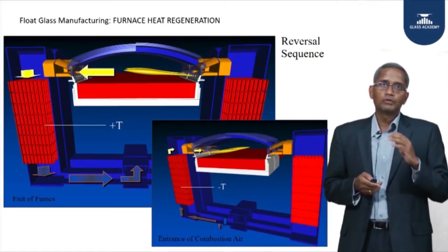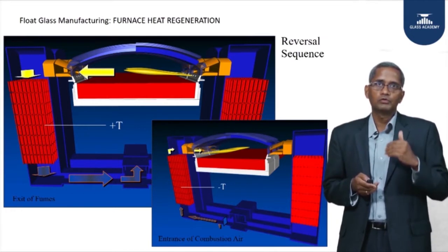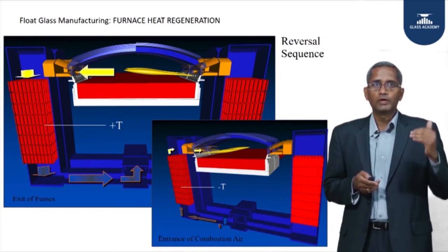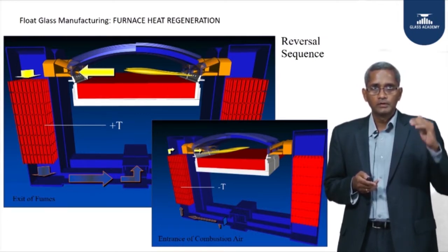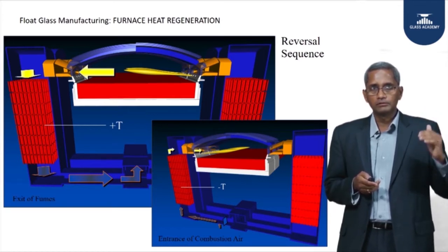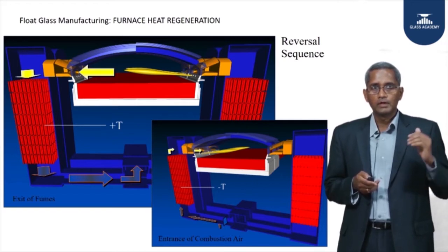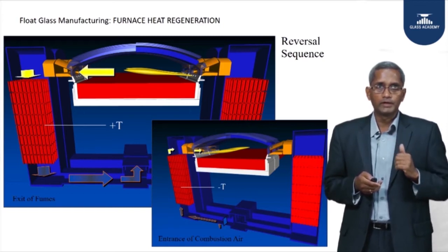In this process, for 20 minutes firing continues from the right hand side towards the left hand side, as seen in the background picture. The flue gas at high temperature goes down through the regenerators. At 1450°C, the heat from the flue gas is absorbed and stored in the regenerators, and the flue gas is wasted through the chimney at 450°C.